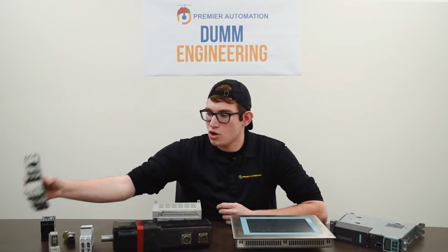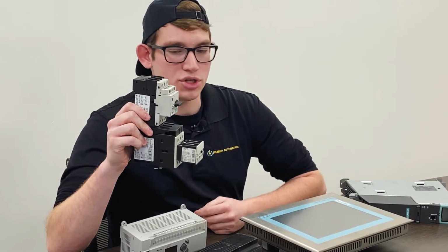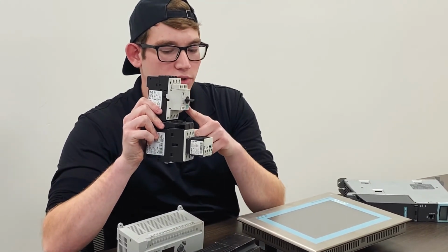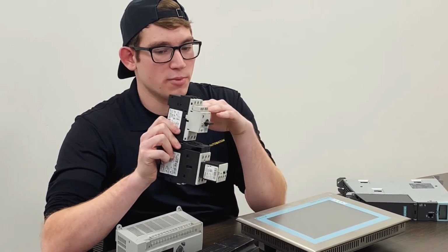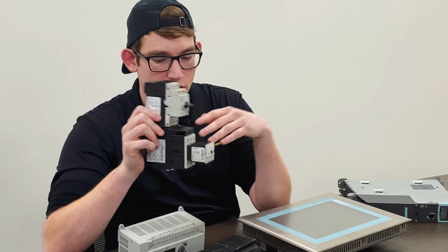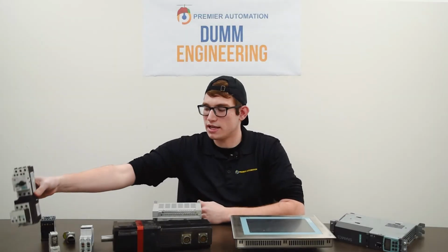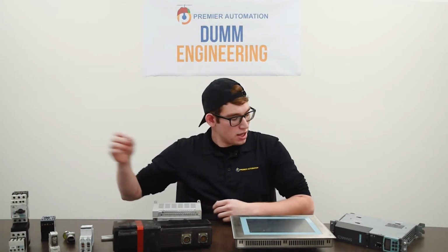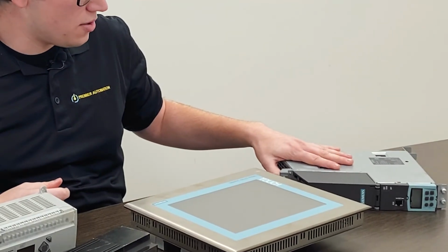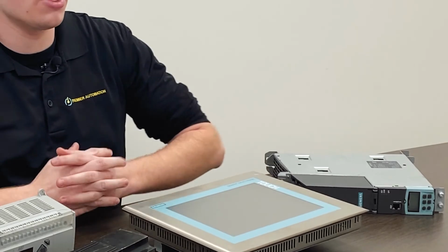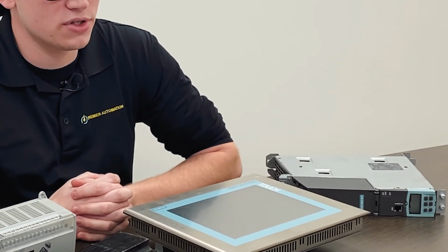In the case of powering motors, in the hardwired versions, we have motor starters, which use a circuit protection and thermal overload, a contactor which allows for control, and in other cases where we might just have a breaker instead of an MSP, we would have an overload on the end to provide that same thermal protection. In the programming world, we use drives, which allow someone to configure things and set many different parameters that you otherwise can't get with a hardwired soft starter.